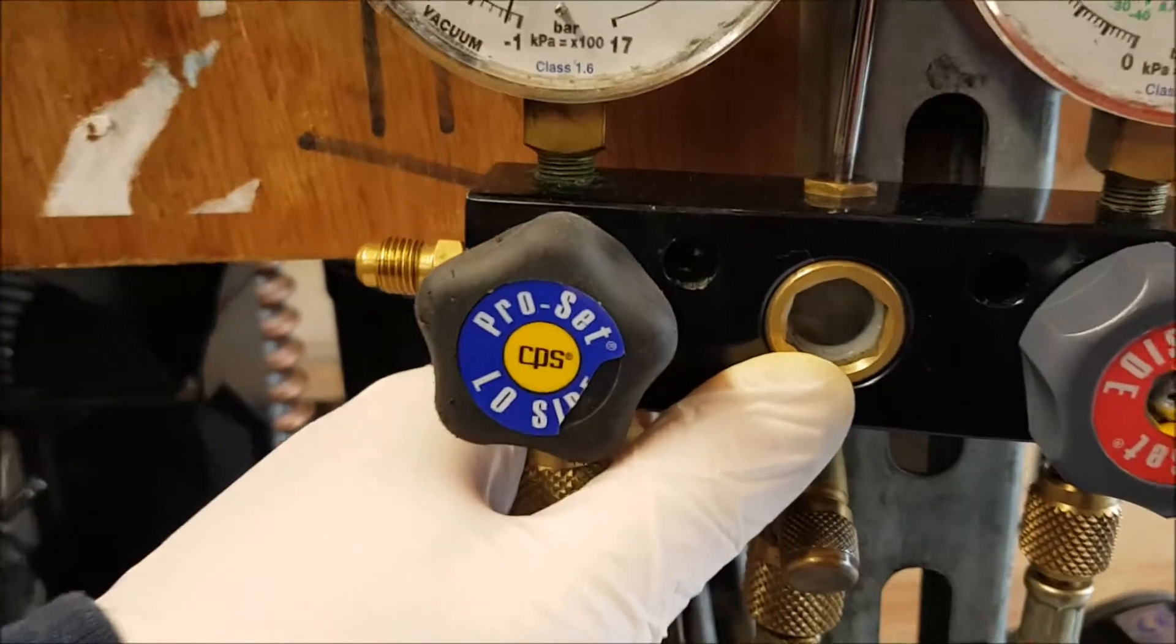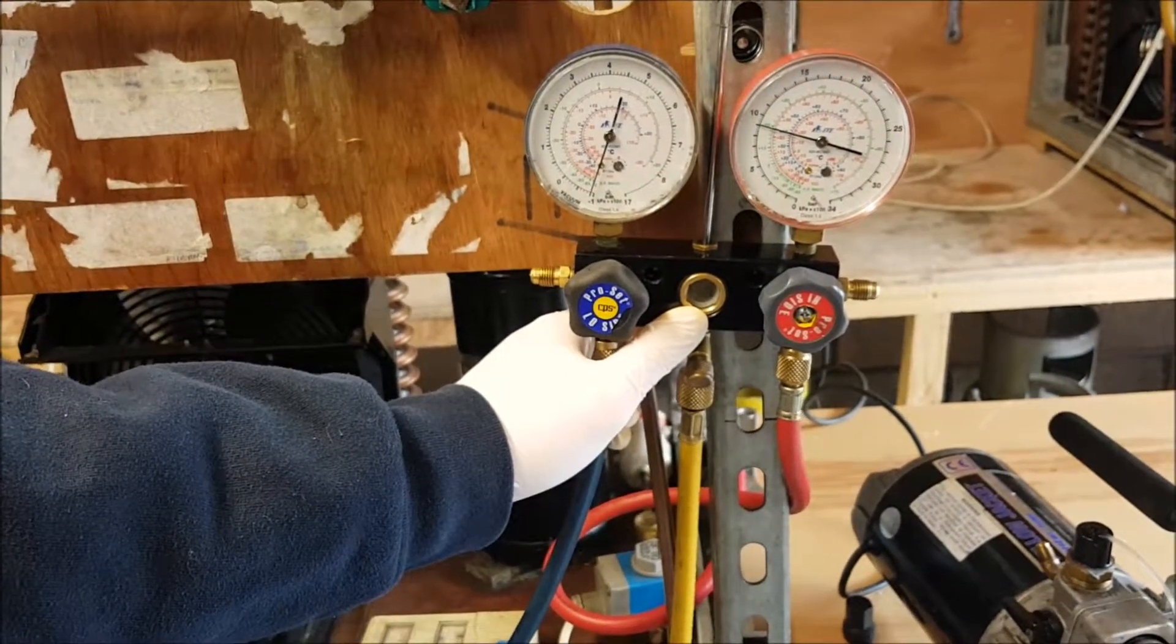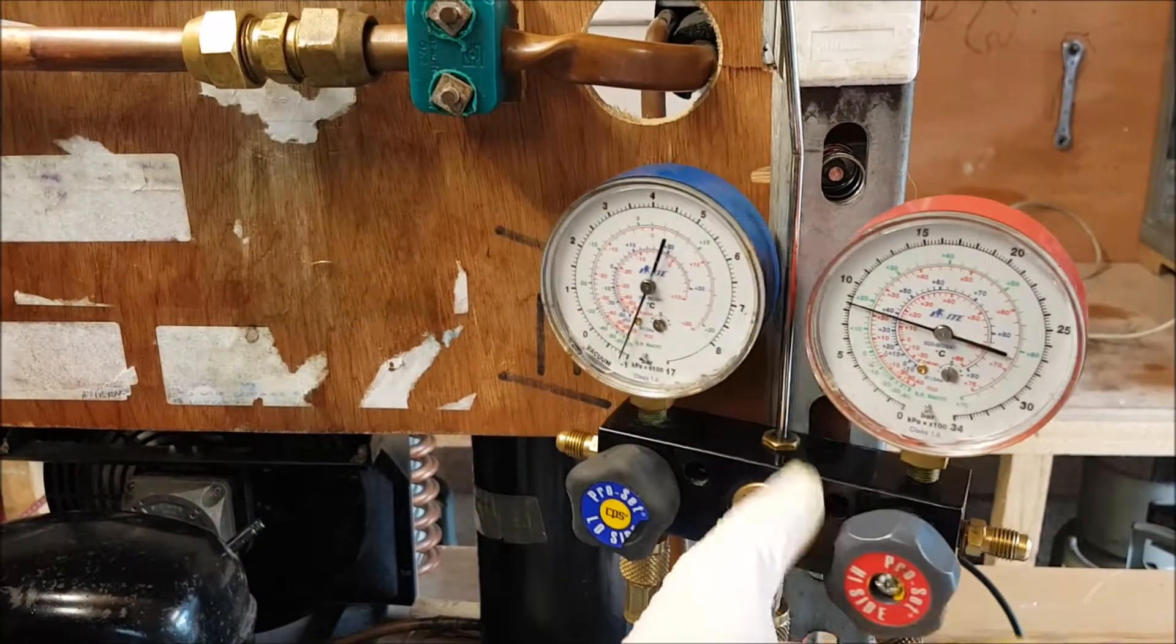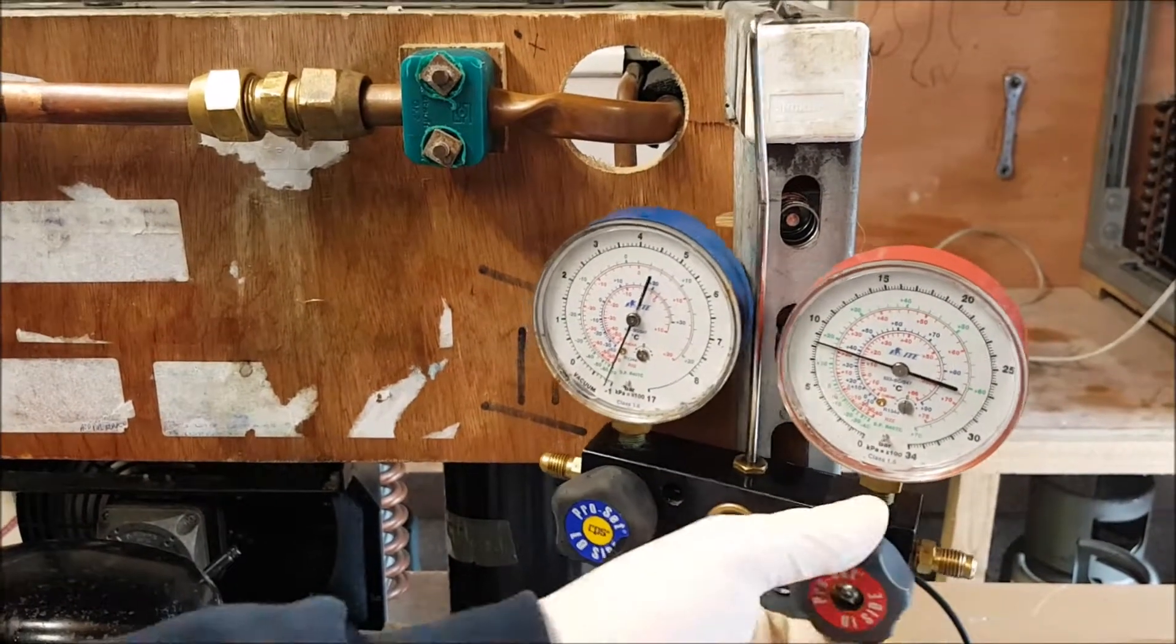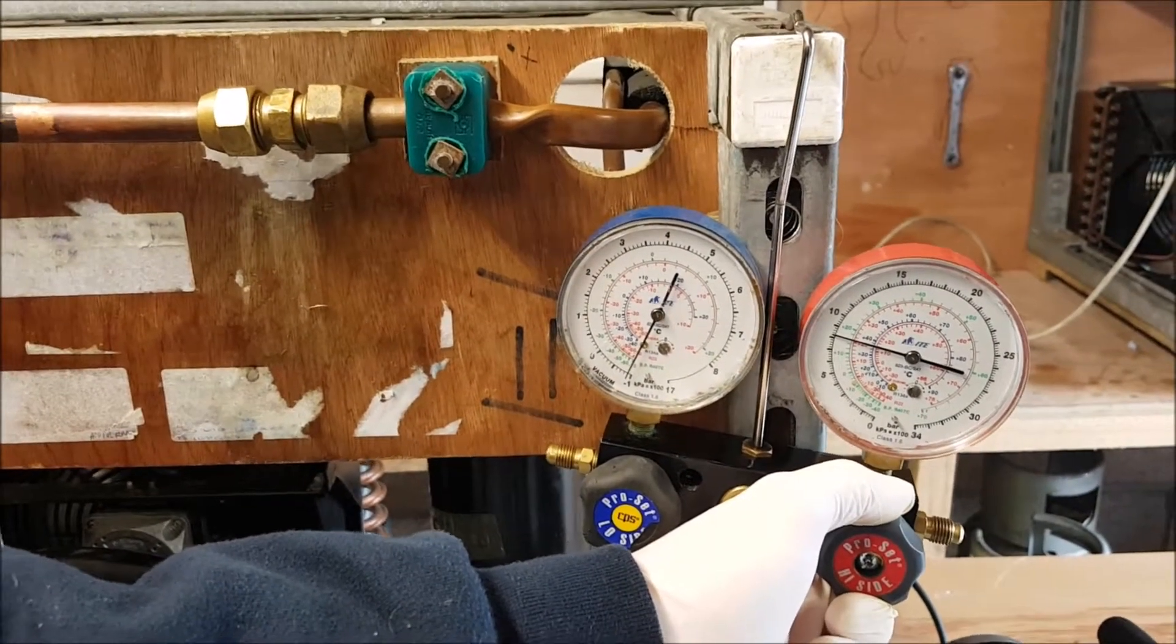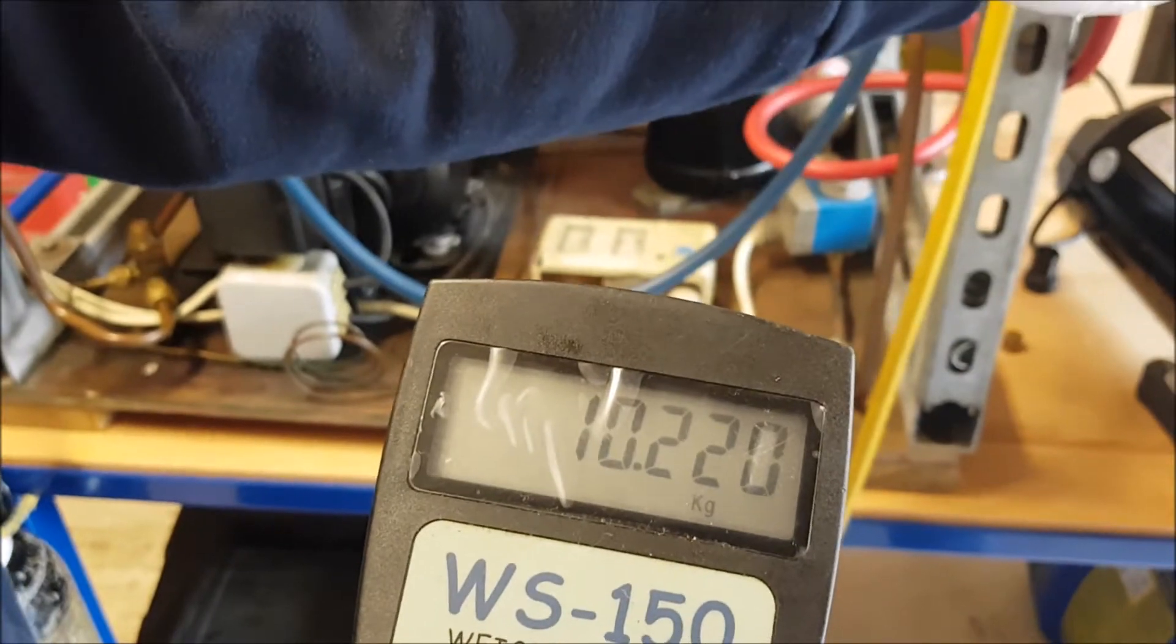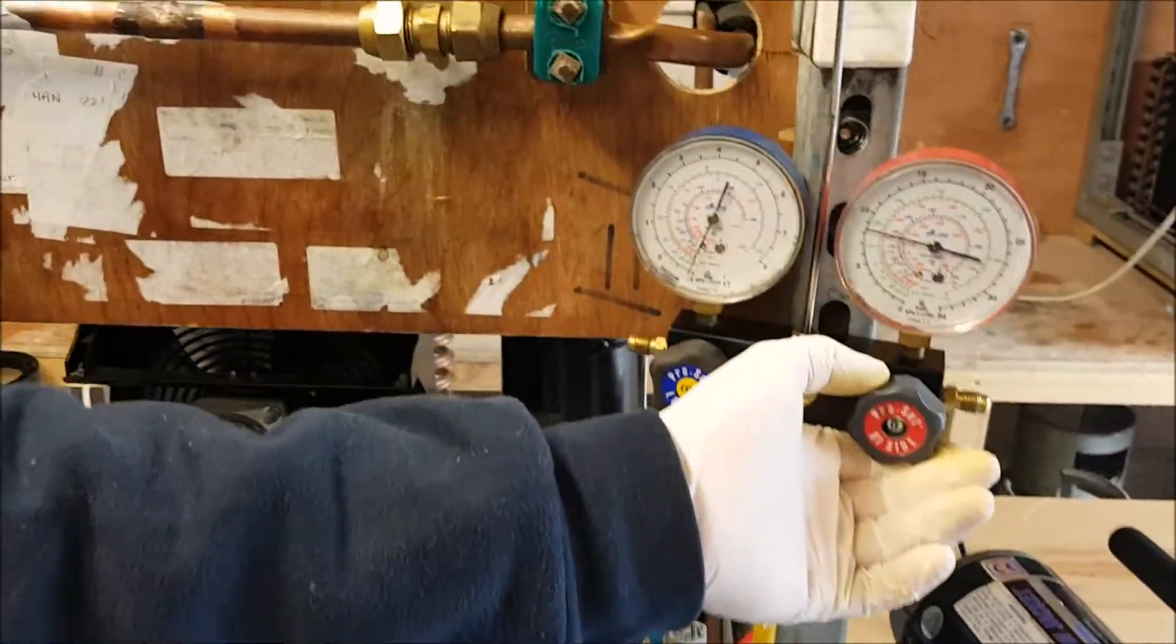If I don't know, then it's up to me. If it's not labeled, it's up to me to weigh it in, commission it properly, and then decide. You can see I've just opened up, the bubble's gone through the high side. There's no liquid getting to the vapor side. You can see my gauge going down, 10.3 or whatever. When this was at standing pressure, it was at just about 10 bar. I'm going to go by pressure. If I decide I need to figure out how much more refrigerant goes in, I just close off my bottle. I can see I'm at 5, 6, 7, 8 bar. I'm getting close to what it was. You can see how much I've moved in. We've gone from 10.63 to 10.23. I'd write that down and do my calculations so I could put on the label how much refrigerant, but I'm not done yet. This is just the initial bomb charge.